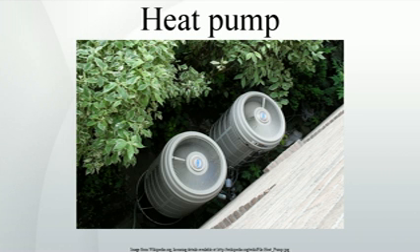Also, as the heat pump takes heat out of the air, some moisture in the outdoor air may condense and possibly freeze on the outdoor heat exchanger. The system must periodically melt this ice. When it is extremely cold outside, it is simpler, and wears the machine less, to heat using an electric resistance heater rather than to overload an air source heat pump.